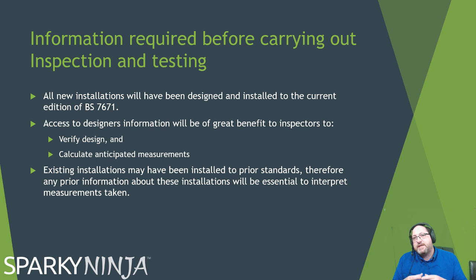Something else you'll need to study is the information required before you carry out an inspection and test. The initial verification has to be done during and on completion, and so you'll need to have design information. This design information must be to the current standard. Access to design information will be of great benefit, so you can verify the design and calculate anticipated measurements. You may have information that tells you what a conductor's size and length is, so you can verify that. Existing installations may have been installed to prior standards, therefore if we can have previous test information, we can then measure and compare to it. Previous information is very, very critical if we're working on existing systems.